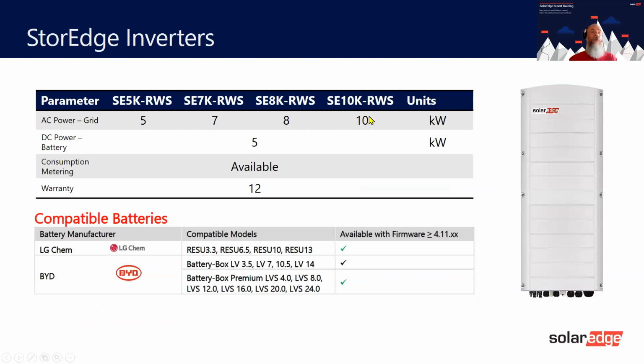Now, obviously, if you're doing this as an AC coupled system, you don't want an inverter bigger than 5 kilowatts, because that's the maximum that the battery will discharge and charge at. So an AC coupled inverter bigger than 5 kilowatts is not really going to help you at all. The warranty is 12 years, and these are the batteries available. The biggest one at the moment is the 24 kilowatt one.